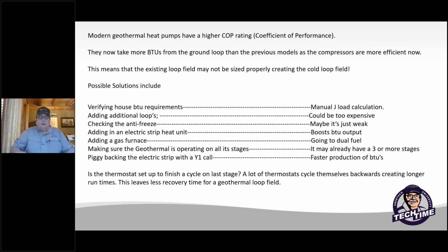Finally, one other piece of information I would like to discuss is the thermostat in the home. Now, coming from northern climates, we start seeing issues with multi-stage thermostats with electric strip heat, right? So you would go first stage geothermal, second stage geothermal, third stage electric strip. But now as the temperature was starting to satisfy, we would see it go from third stage electric strip to second stage geothermal, first stage geothermal, and then guess what? It had to start ramping back up again. So second stage, third stage, and so forth.